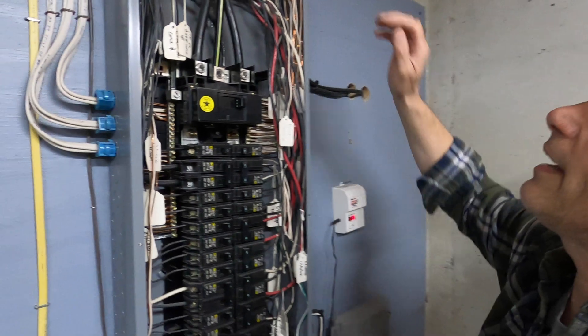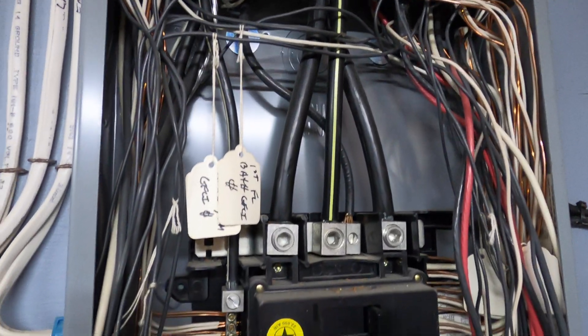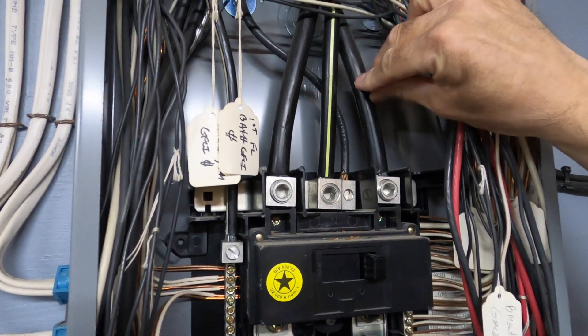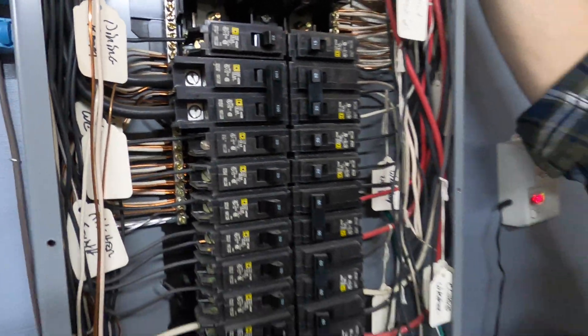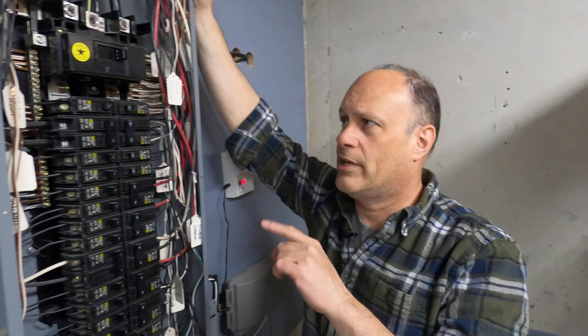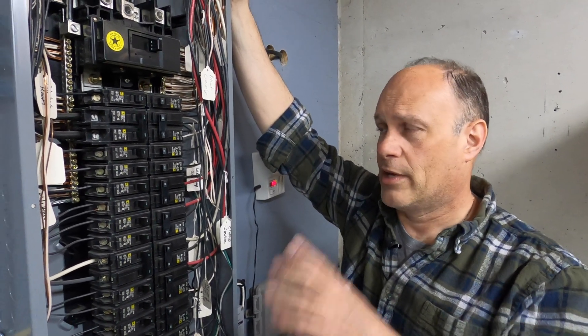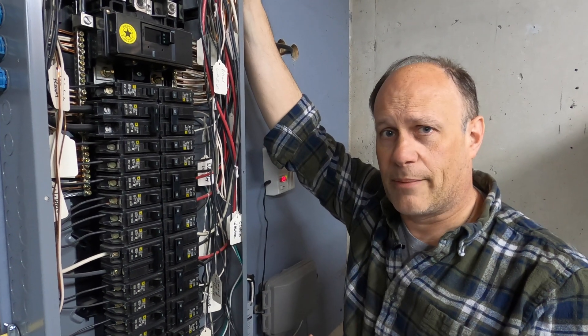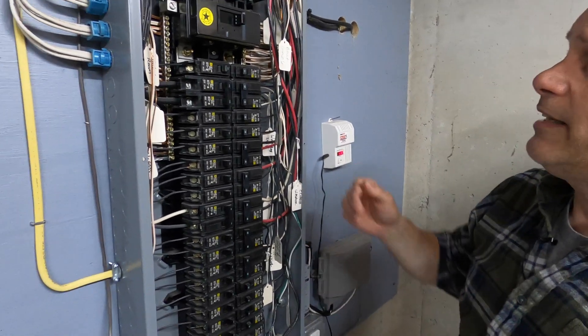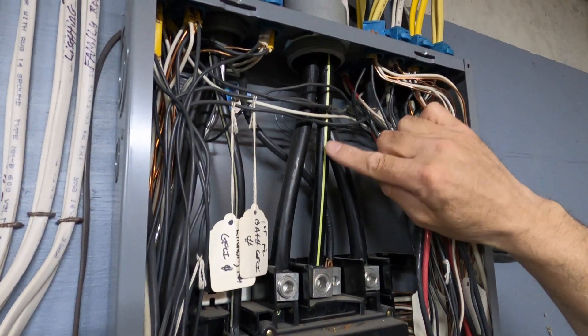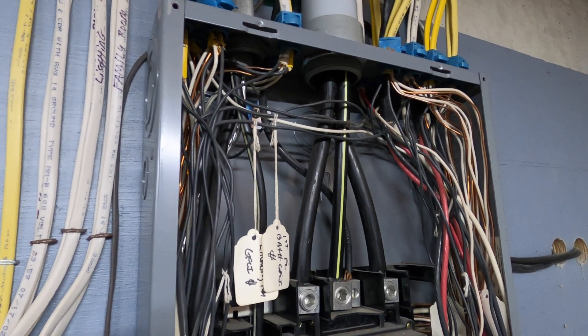This is the inside of our panel box. And I just normally do a quick inspection for the homeowner. One of the things I can see that this is type URD cable. And there's a lot of energy inside these boxes. There's arc flash hazard, electrocution hazard. This is a very serious thing. So you really want to be very careful and just respect what you're doing and take your time. And again, with my inspection, the panel looks clean. I can see this is an underground service because this is a type URD cable. It's a direct burial cable outside.